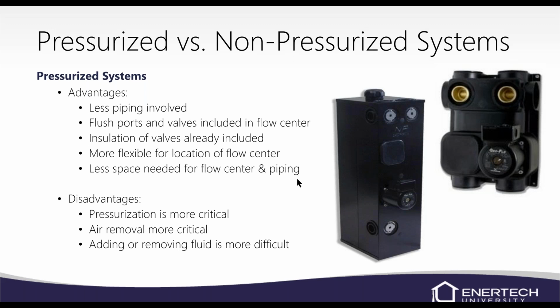Some of the disadvantages of a pressurized system over a non-pressurized is obviously it's a pressurized system, so pressurization is critical. If you don't have pressure, the pumps will cavitate. You got to have, I think it's like 2 psi to prevent those pumps from cavitating. So in a pressurized system, the pressure in the loop field gives it that pressure so the pumps don't cavitate. In a non-pressurized system, it uses the standing column of water in that tank to provide the pressure so the pumps don't cavitate. Obviously, air removal is more critical.